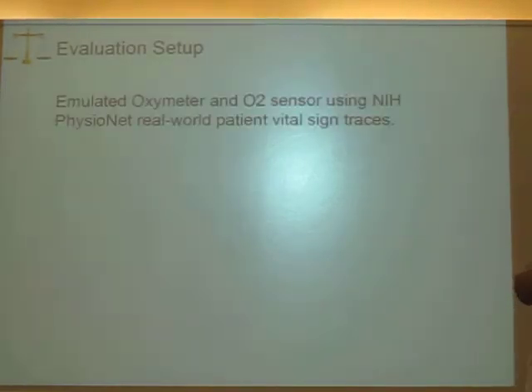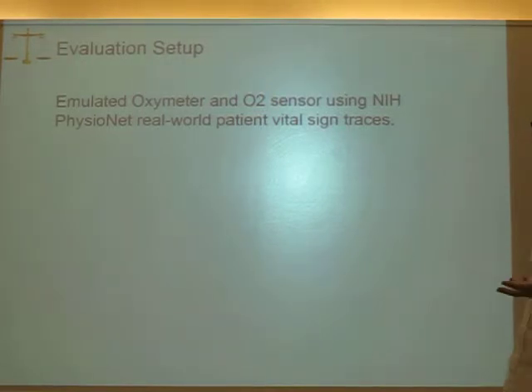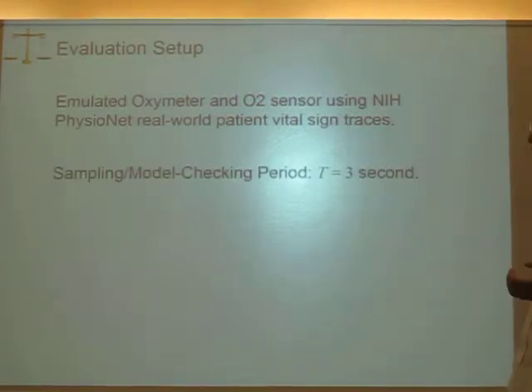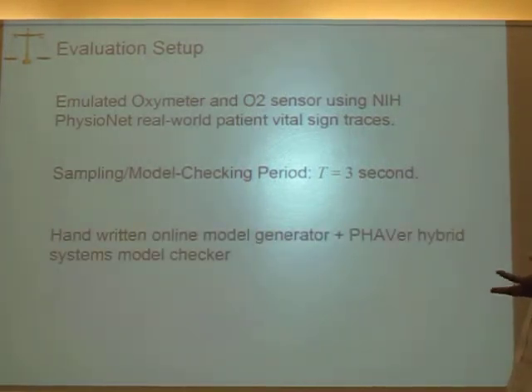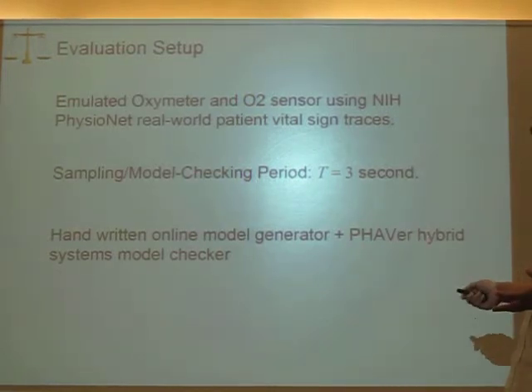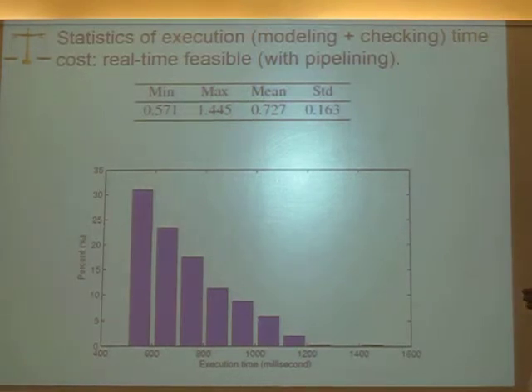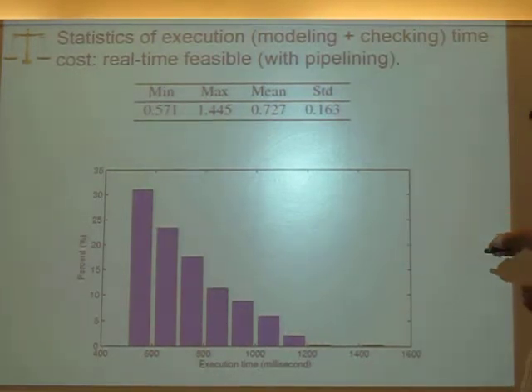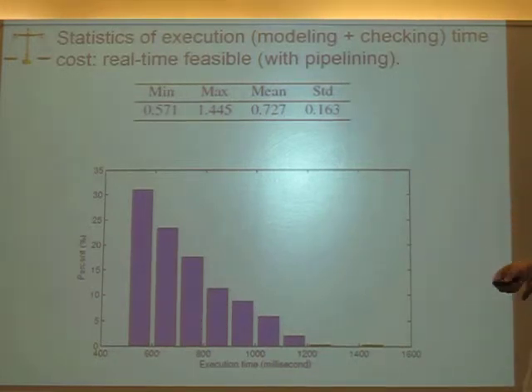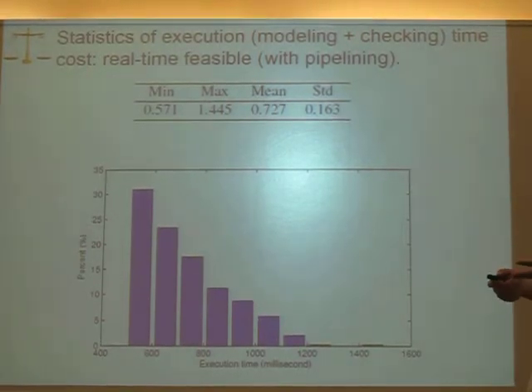Evaluation. We emulated the oximeter and oxygen sensor using NIH PhysioNet real-world patient vital sign traces. The sampling and online model checking period is three seconds. We use a handwritten online model generator combined with a well-known hybrid system model checker called PHAVer. The computational environment is a very mediocre laptop environment. We find that the modeling and verification time cost is always within 1.5 seconds. Remember, the online model checking period is 3 seconds, so with simple pipelining, we're confident that the model checking can be carried out online and within real time.